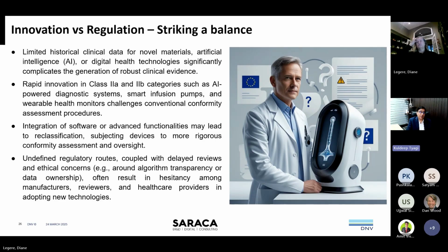I think we might have done probably 15 to 20 tech files which were written, and we had to rewrite all of them because SaMD, software as a medical device standard, was not really followed. The traditional device did not really have software, and the manufacturer had a small piece of software and didn't realize that they have to follow 62304, integrate the software, and do a lot of testing again. It's a very important aspect.